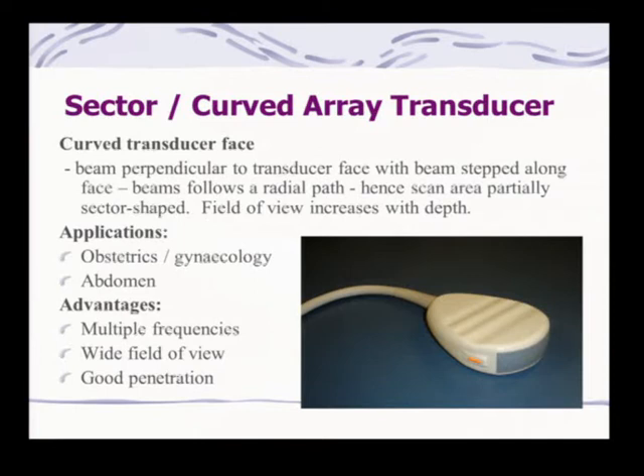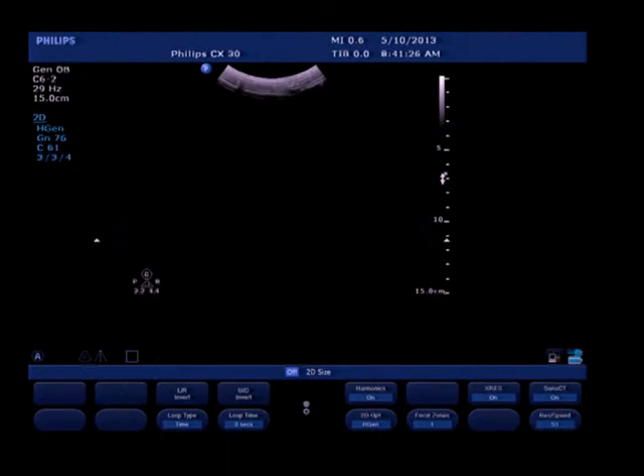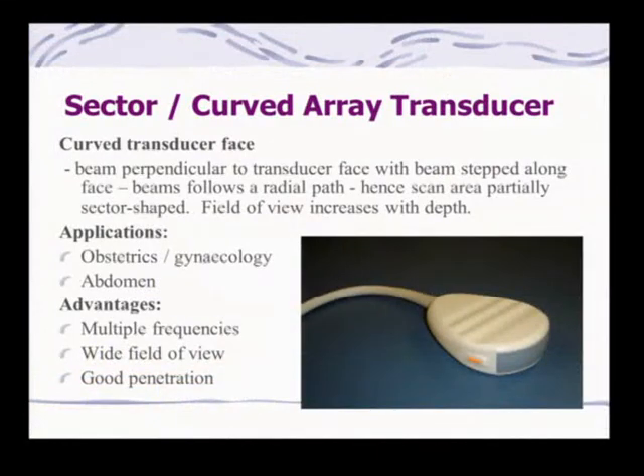So we've got a few different types of transducers that you can use. We have our sector or our curved array like this one, which is the most commonly used for obstetrics. The beam is perpendicular to the transducer face, but it's stepped along the face and follows a radial path, so the scans are partially sector shaped. And Tracy, have you got one of those plugged in? Yes, I'm just going to switch across. So this is the sector, and you can see at the top how it's curved. The advantages of that are multi-frequencies, a very wide field of view, and quite good penetration.